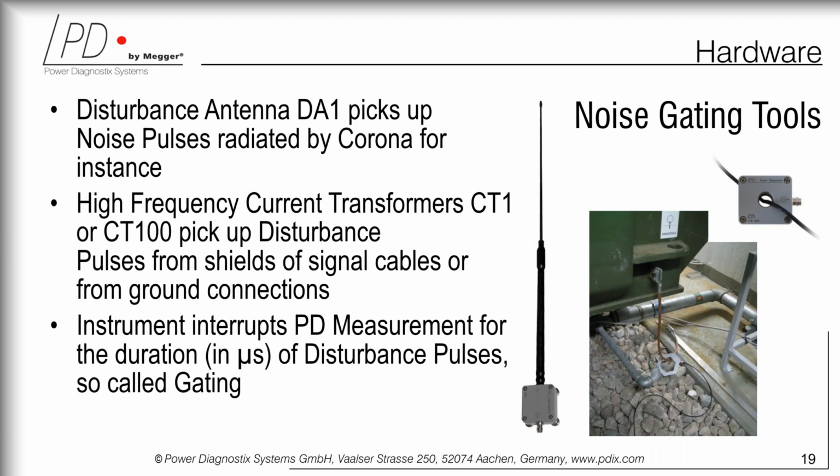I'll be honest, mounting such antennas is a tricky thing because obviously they will pick up a wide variety of signals. So generally people prefer to have the bushing couplers and also the hatch or oil valves for UHF signal. But this antenna is a noise gating tool, and it has its own benefit when employed in conjunction with our devices.